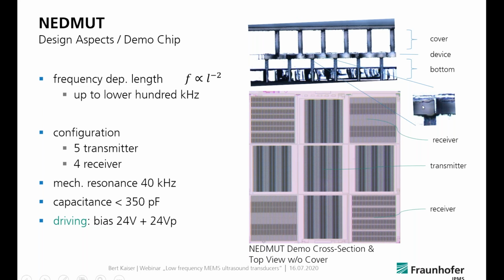And I made here a zoom picture of the very small actuators moving in the active layer of the layer stack. These actuators here in the clamped version have a certain thickness, length, and geometry, so the electrode shape, which is describing the performance of the actuators. And from the length, you can roughly guess which frequency range we can address with this technology. And if you use this rule of thumb here, you can easily estimate that we can go to the lower 100 kilohertz range, which is the topic of this slide set, low frequency ultrasound transducers.